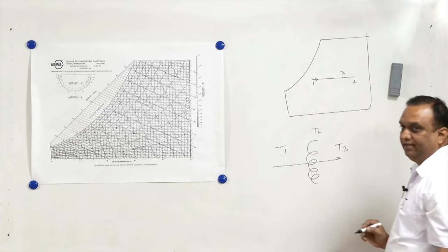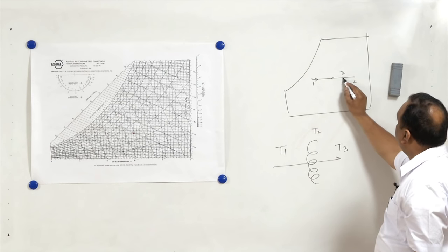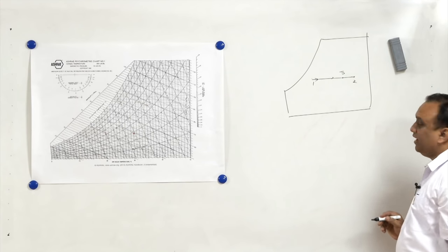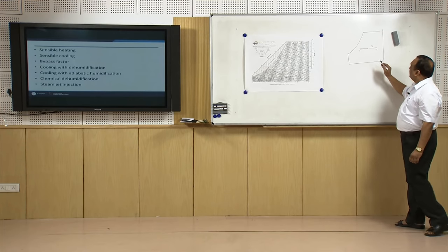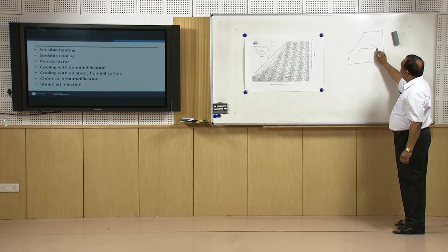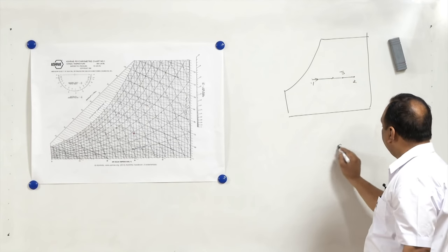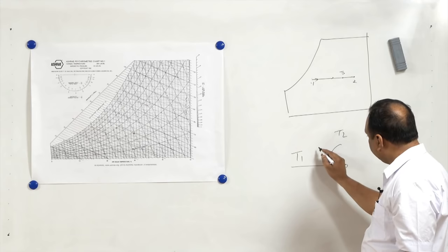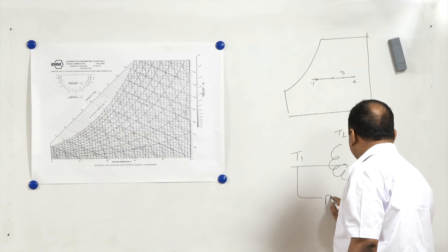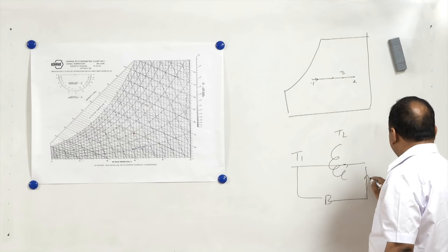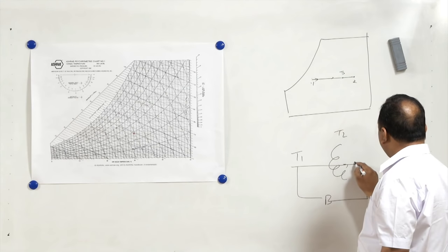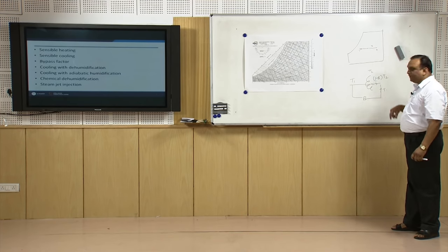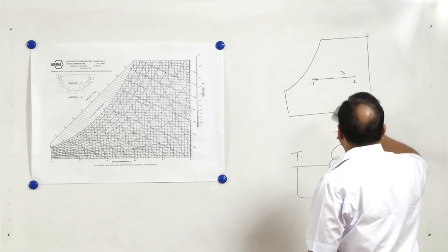This temperature difference results in the bypass factor. Why is it called bypass factor? We say that part of the air has attained temperature T2 and part of the air is bypassing the coil. So, if the air is going in this direction at T1, this is at T2. Some fraction of air is bypassed and remains at T1, and the air which is blown over this coil attains temperature T2.